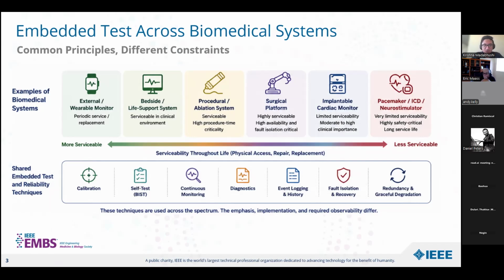However, the consequences of a fault during an active procedure can be much higher. In that situation, knowing that the system can be repaired later is not enough. The fault may need to be detected immediately, isolated quickly, and handled in a controlled way so that the system either continues safely or transitions into a defined safe state. And coming to the implantable systems, they also add another layer of difficulty. The function is highly critical and physical access is very limited. The device can often be interrogated. It can store diagnostic information. It may communicate through telemetry, but it's not available for the same direct measurement we can perform with an external system.